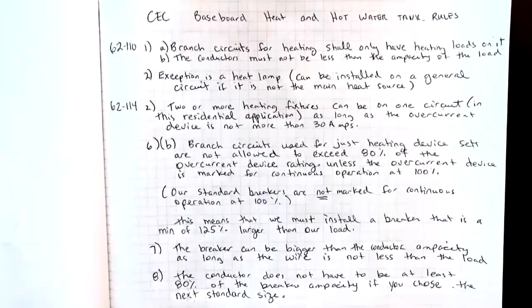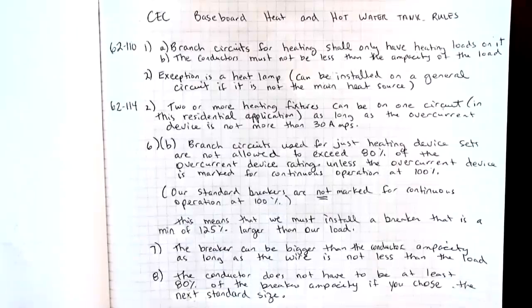We're going to do a short video to describe the rules around baseboard heating and hot water tanks coming out of the 2018 CEC Canadian Electrical Code, Section 62. Rule 62-1101A tells us that branch circuits for heating shall only have heating loads on them. B says the conductors must never be less than the capacity of the load.